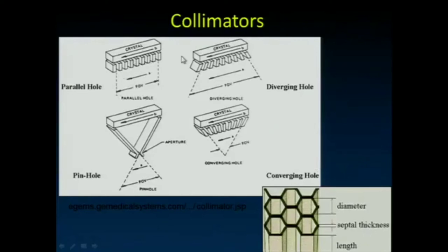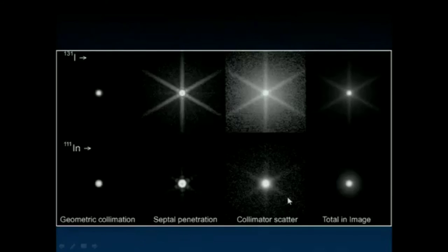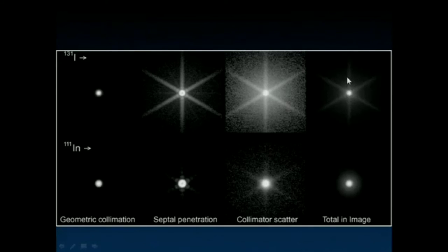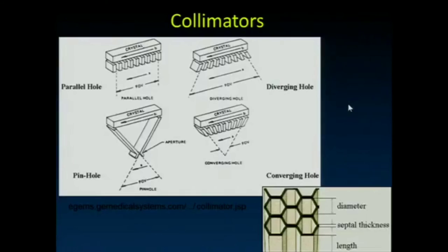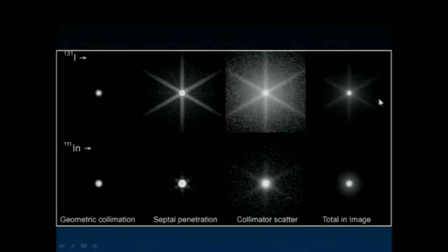Collimators are made from lead, often from corrugated lead pieces that when stacked together form hexagonal holes. For higher energy radionuclides like I-131 — which is a beta emitter but also produces high energy gamma rays — those gamma rays can pass right through the thin lead septa of some collimators. This produces a septal artifact with a star pattern that corresponds to the orientation of the walls in the collimator.